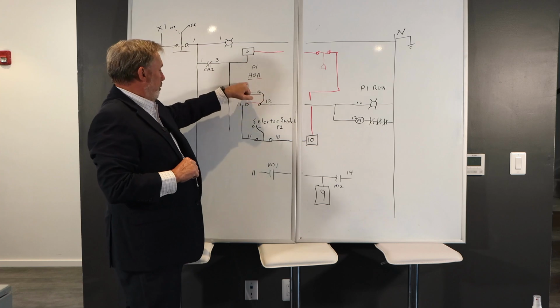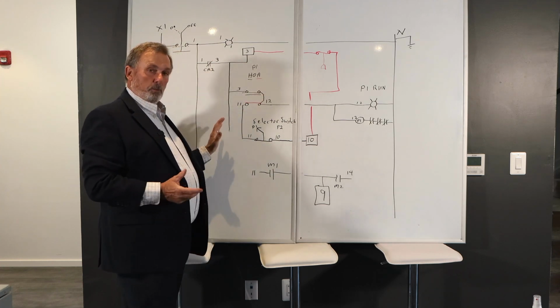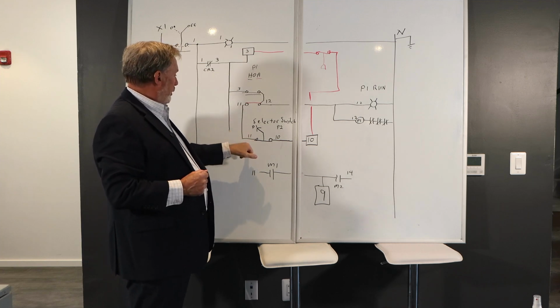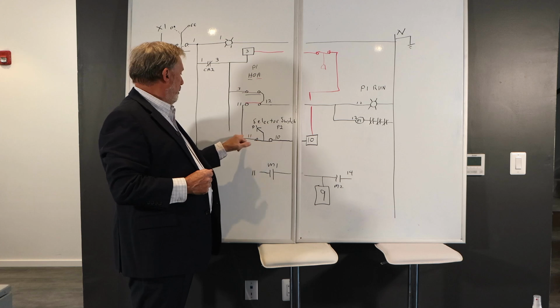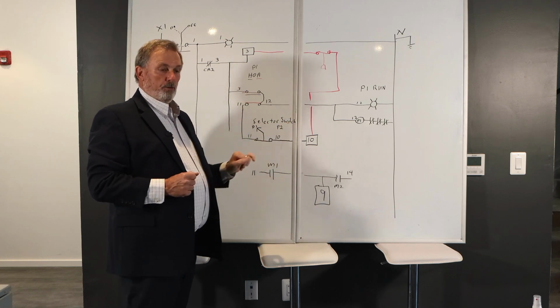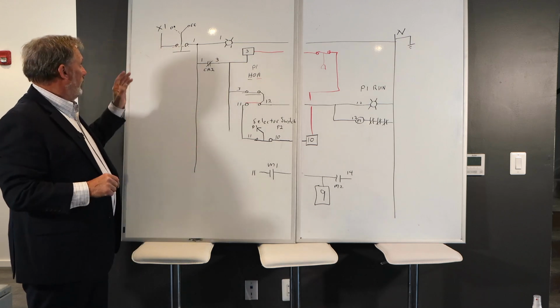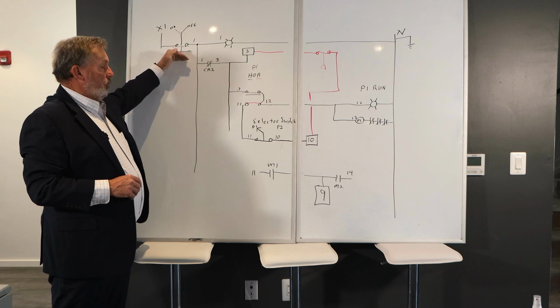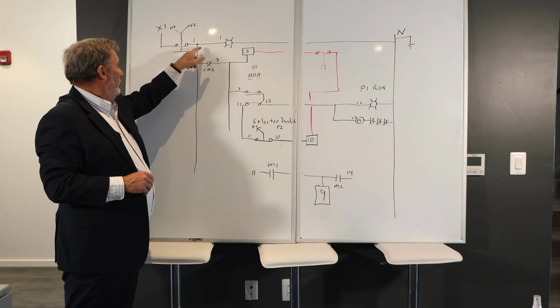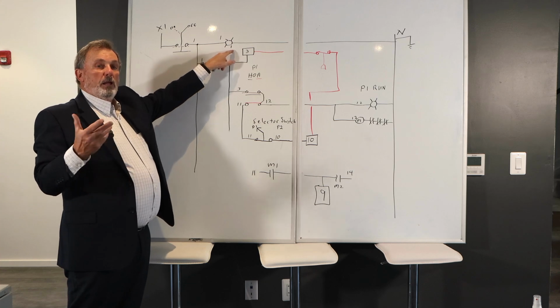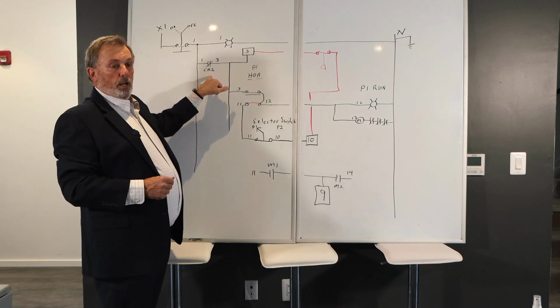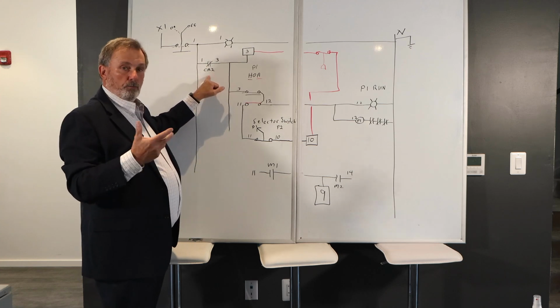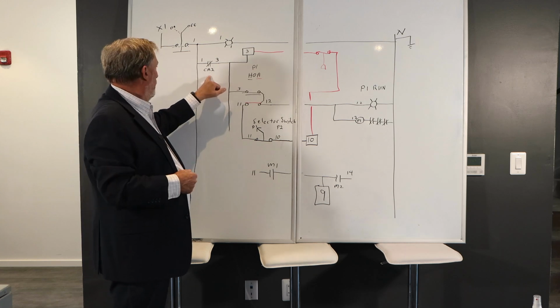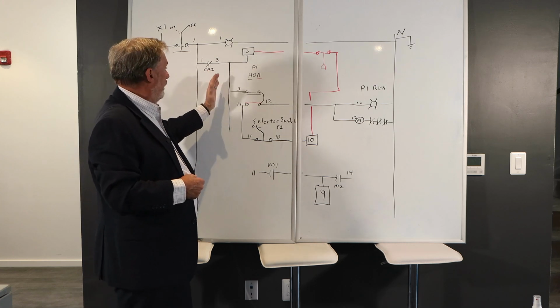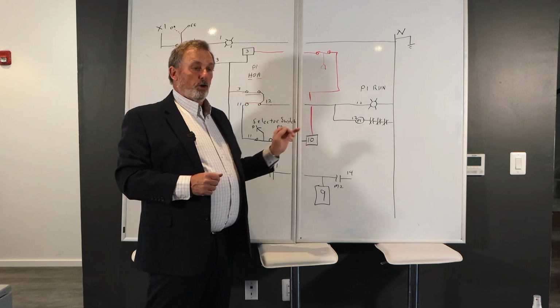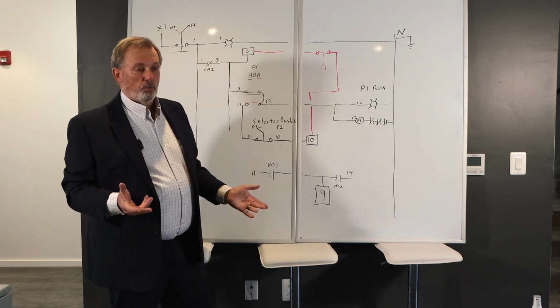The HOA switch, there's one for pump 1, there's one for pump 2. Basically, they're going to be carbon copies of each other. The pump selector switch, I've only drawn pump 1. When I go to pump 2, I'm going to pick up 11 and another number, and we'll draw that in just a moment. So fundamentally here, we've got the 120 volt power, we've got control power on and off, which makes our number 1 right here, our hot, only to indicate that we have power. Off of a control relay, a safety relay, we're picking up all of our voltage, all of our control power is coming off of this safety relay, and that's feeding all of our pump commands. It's also feeding our level switch and any alarms that we're going to have.